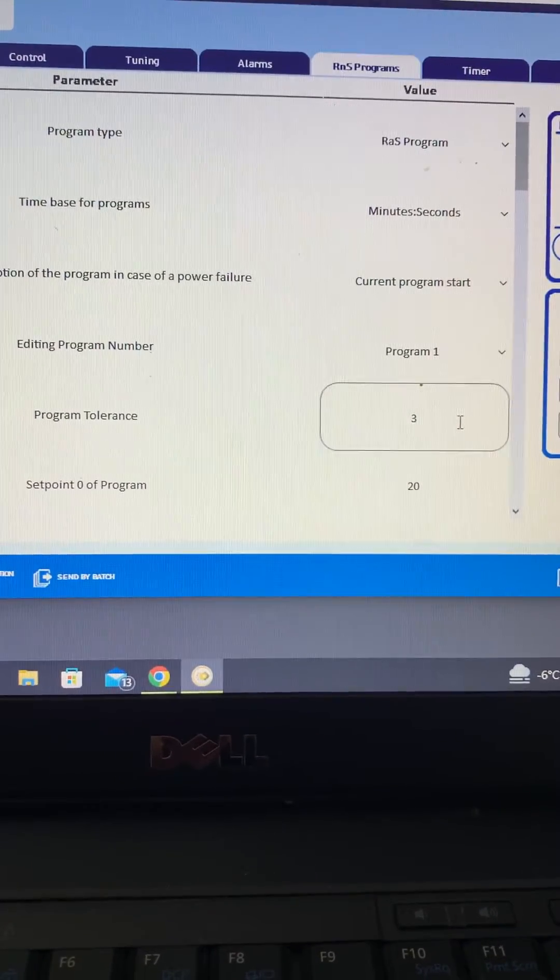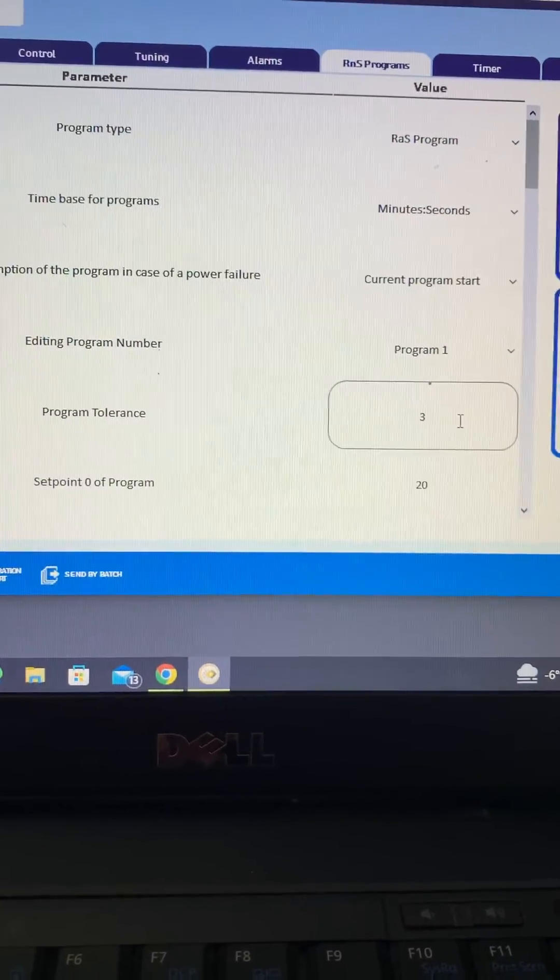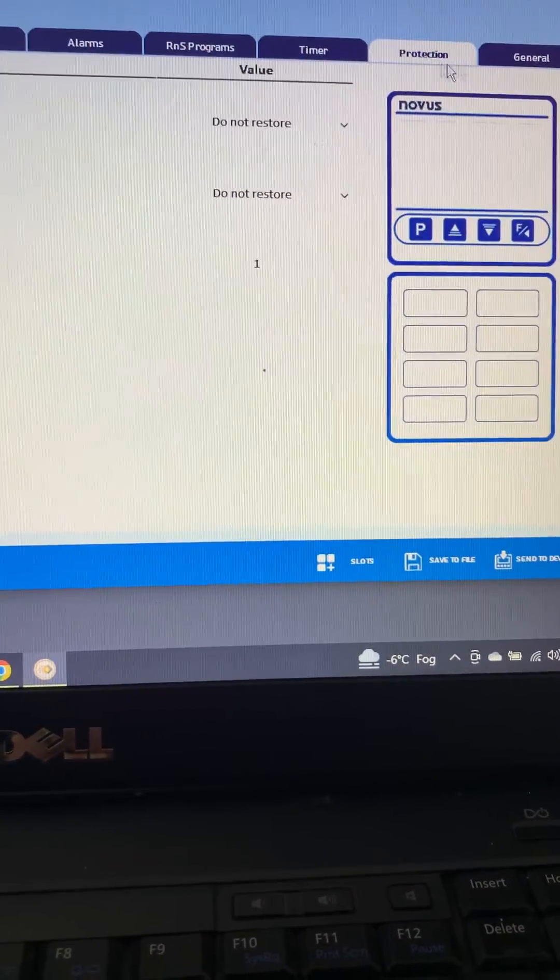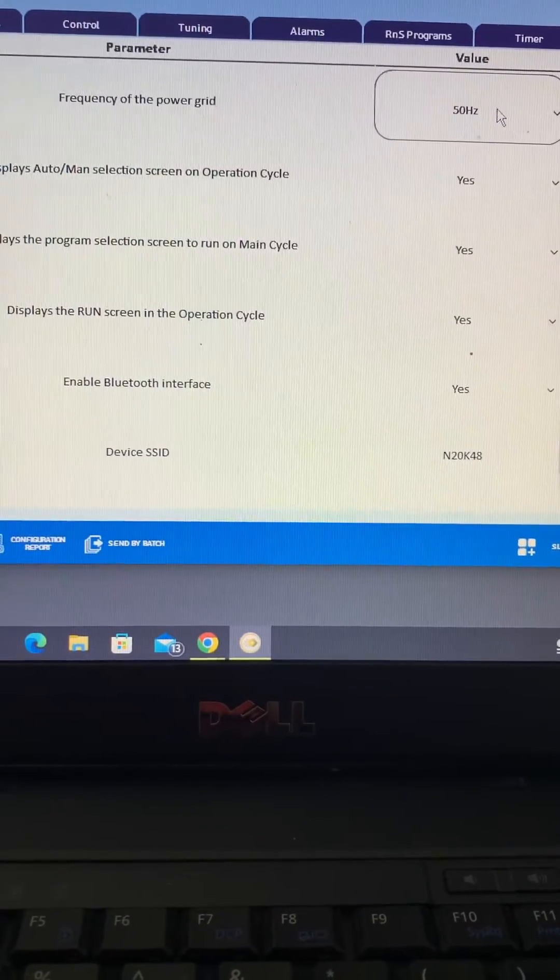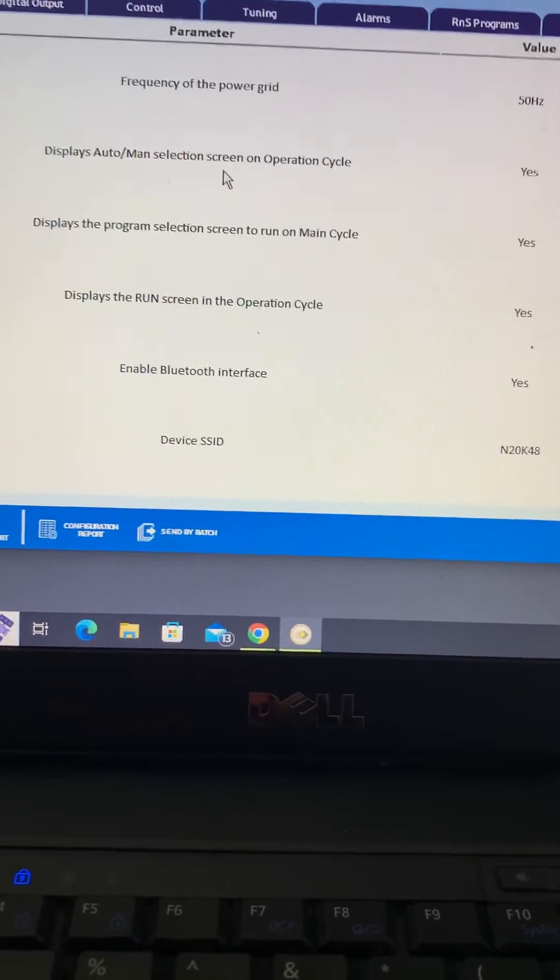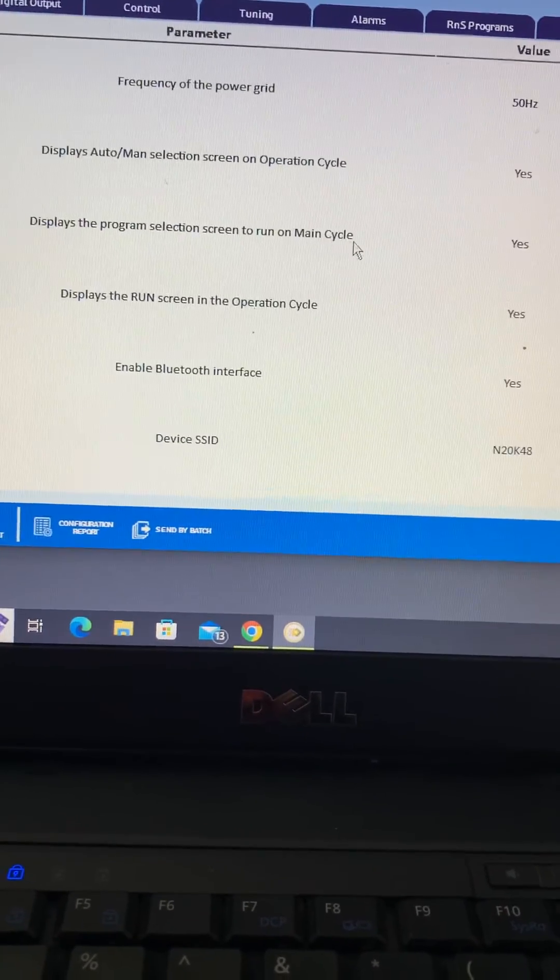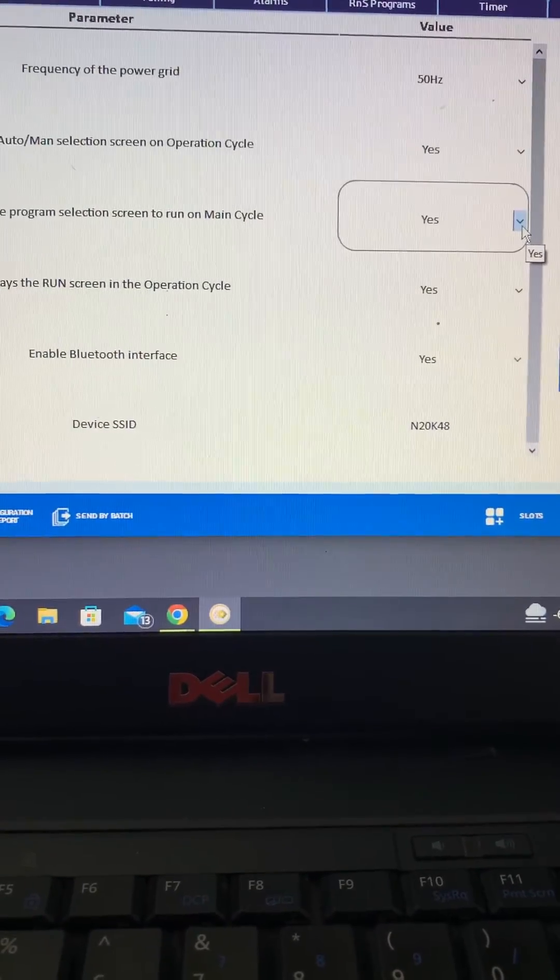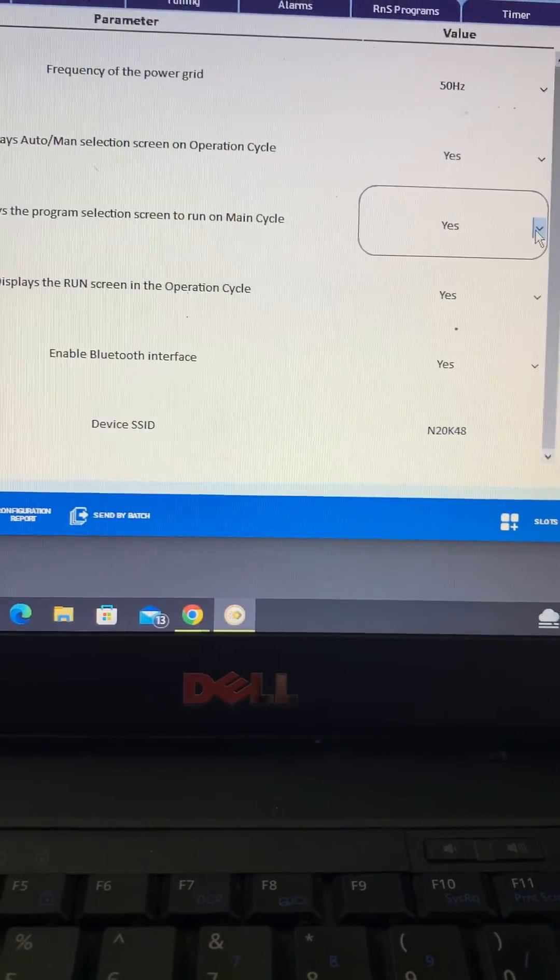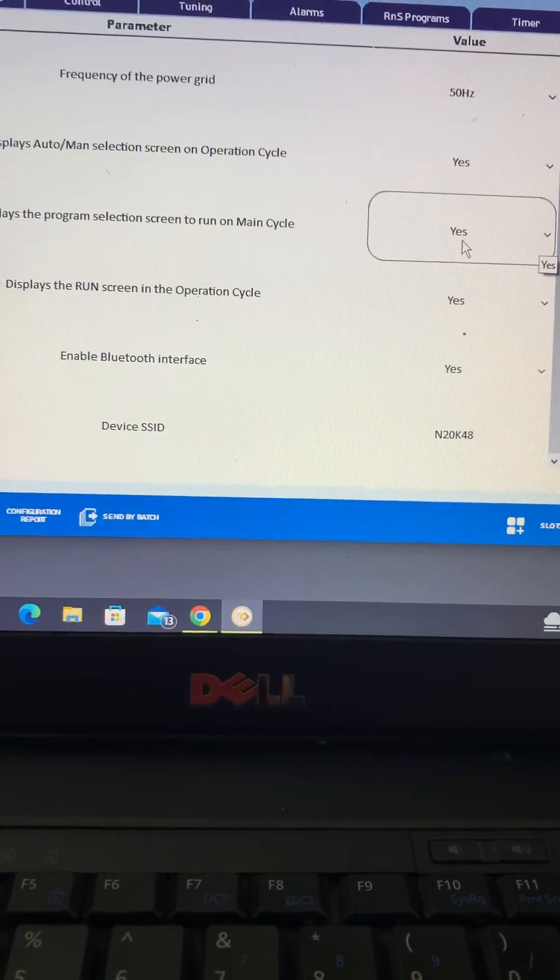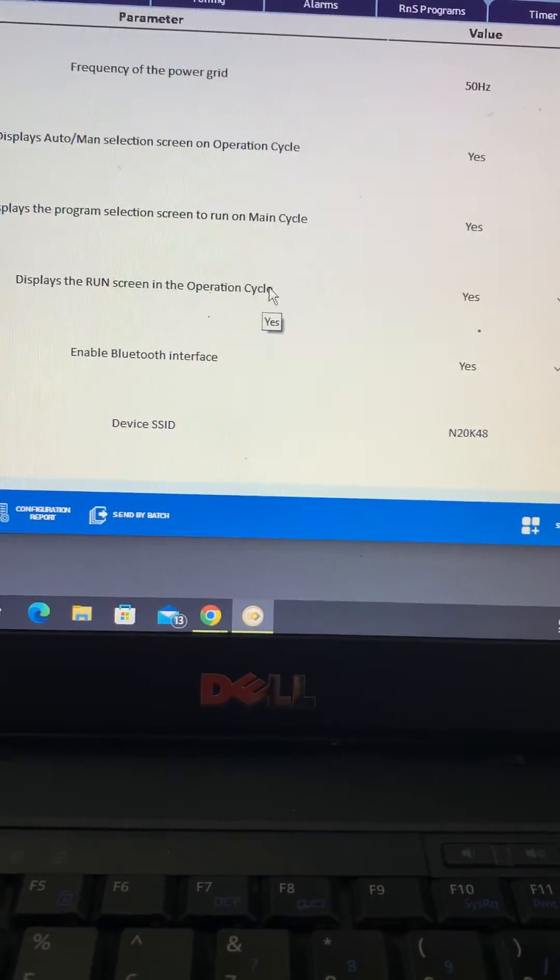Essentially we're not using the timer here, no protection. And obviously you've got your general ones. The frequency of the power grid in the UK, we're on 50 cycles, 50 Hertz. Display in the auto and manual selection screen on, we always go for yes. Display the program selection screen, well that's an important one for a ramp and soak because you want to quickly be able to change between programs or if you don't want a program at all, you want that accessible without having to delve too deeply. So that will all be accessible just with a single tap of the P button from what we would call the operation cycle.